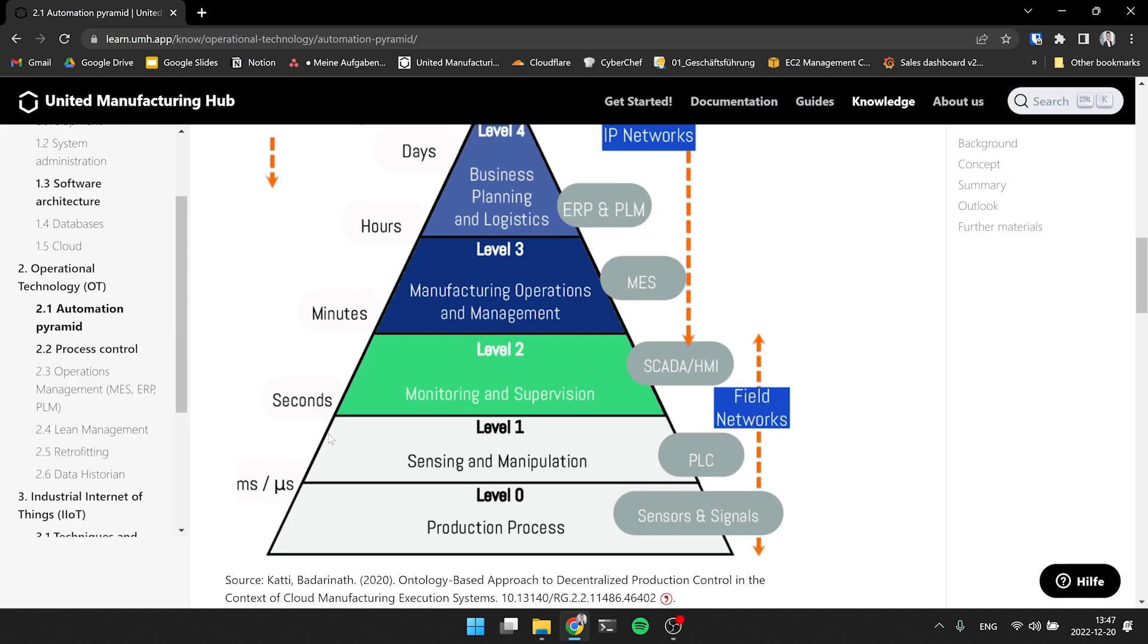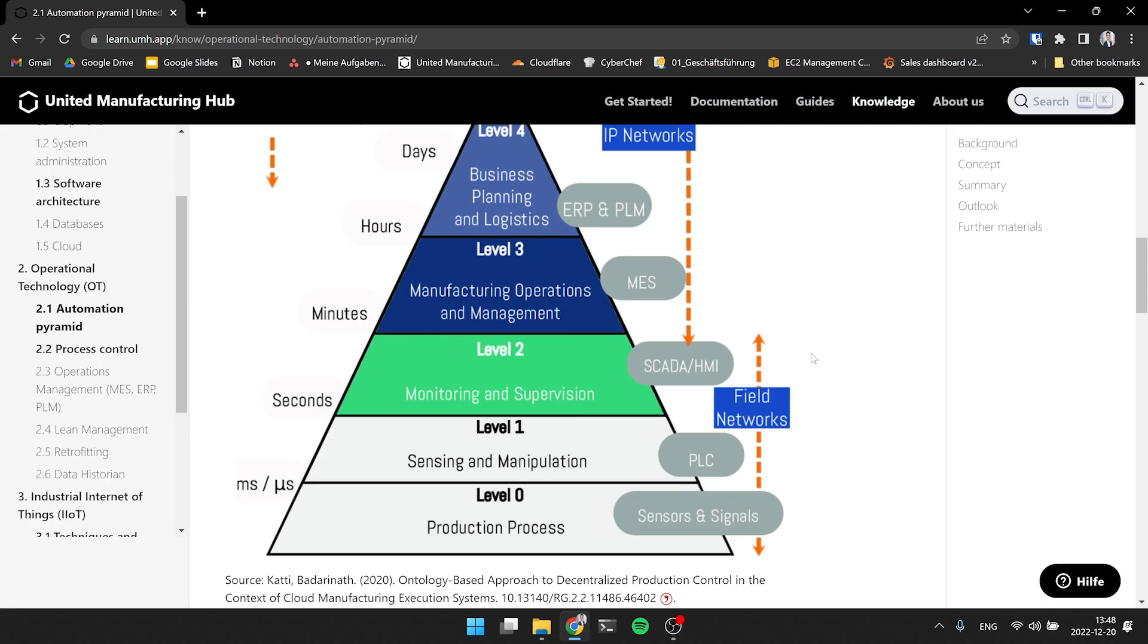So even though you have a production line and the IT connection to the IT system starts here at the MES level, theoretically you have all the data, you have all the vibration, but it's not available because there are elements in between. And you also don't want to change those elements to pass the data through because they are not designed to handle this type of data. So currently, this is one of the problems, everything is in silos. And this is where the concept of unified namespace comes in. We will later talk about it in the chapter of IOT. How can we combine everything? We basically say okay, what about that? We don't only talk with the level above, but we talk to a central point, like a message broker so that we can exchange information even across levels.